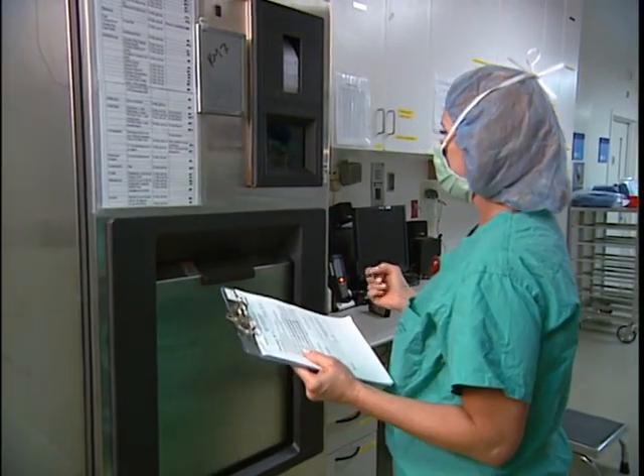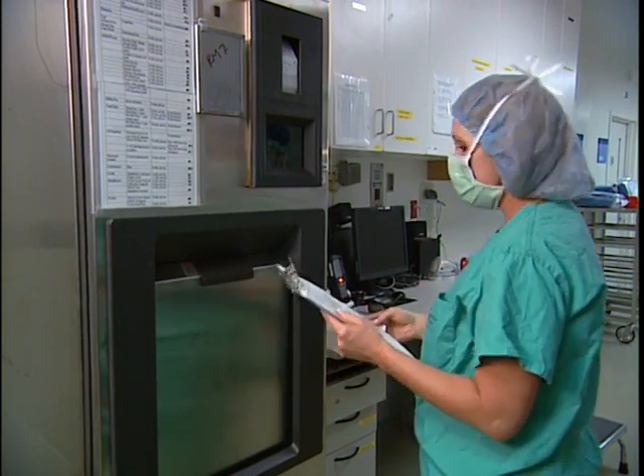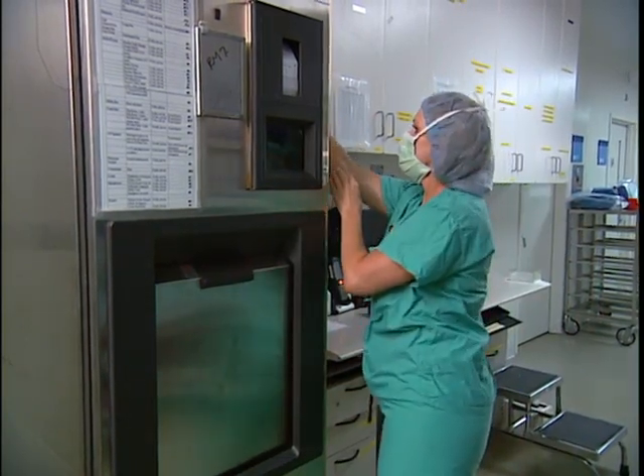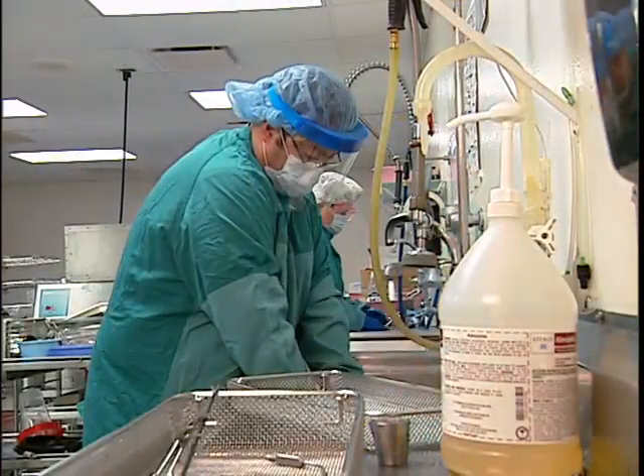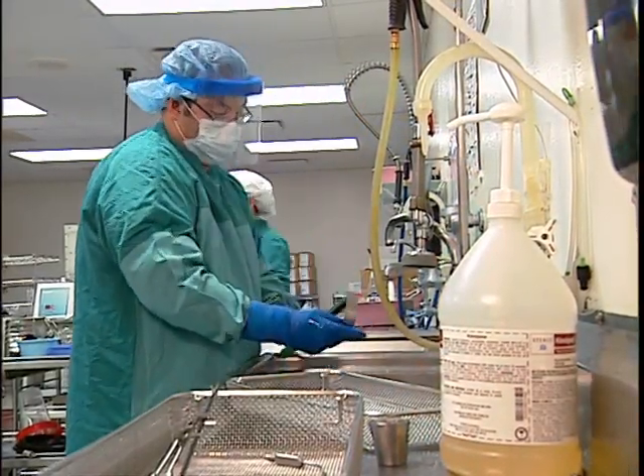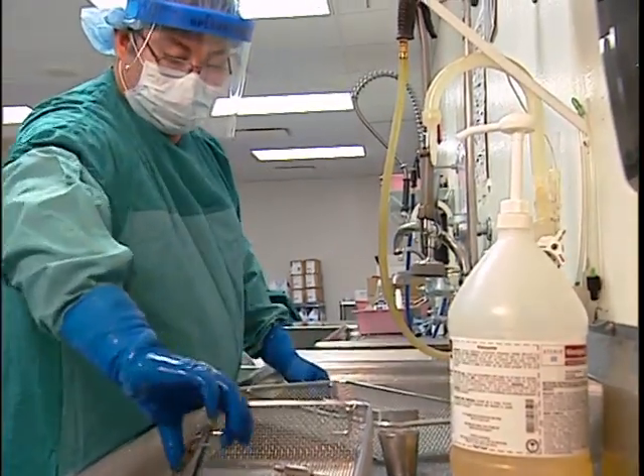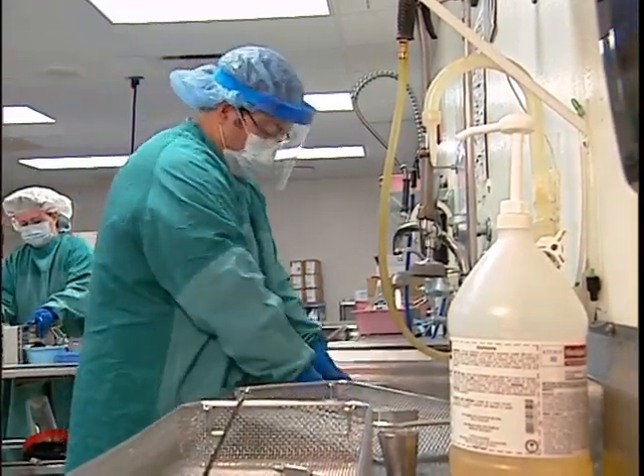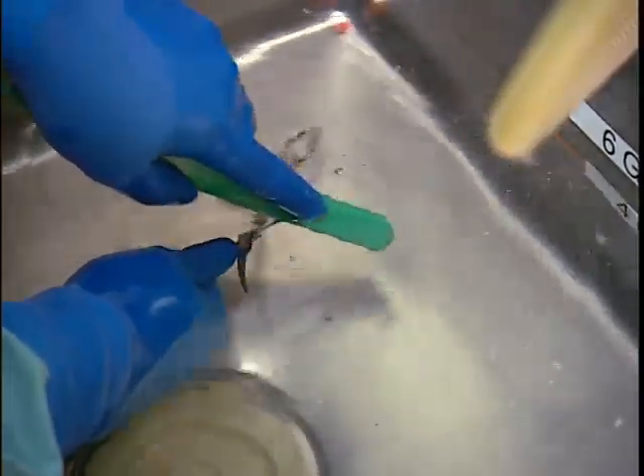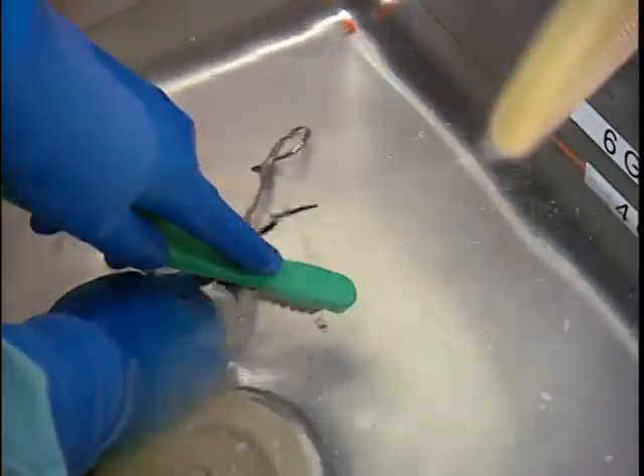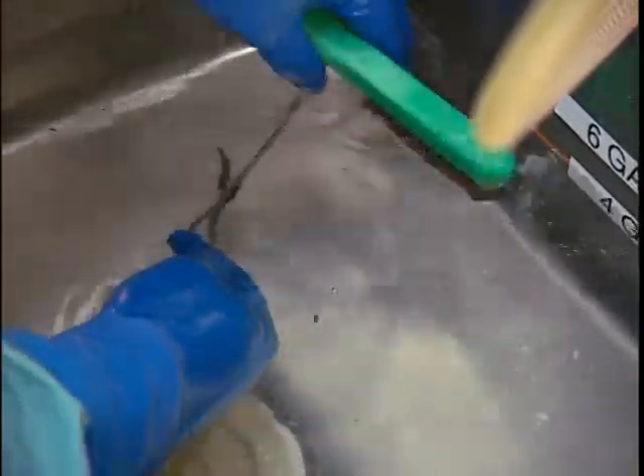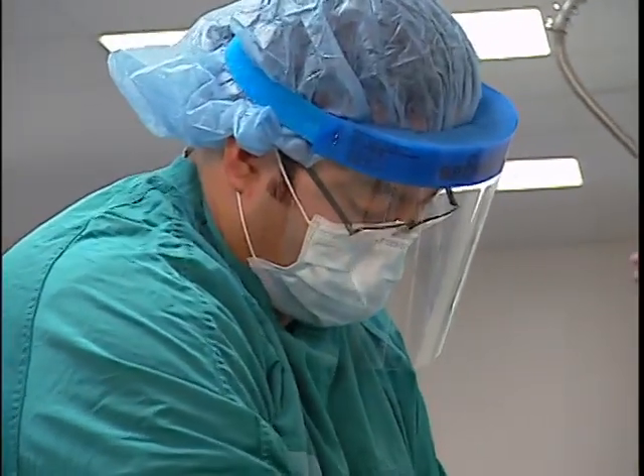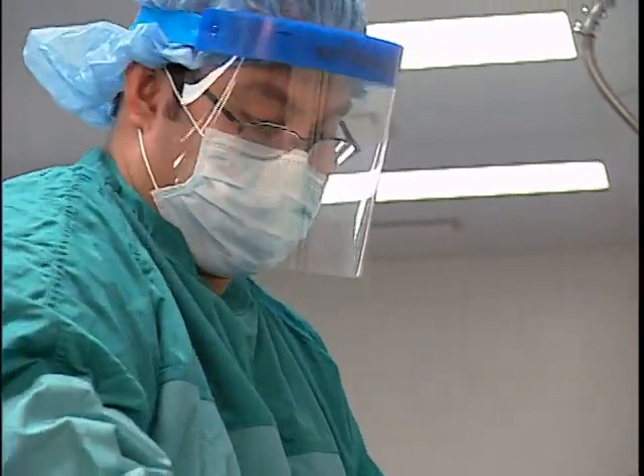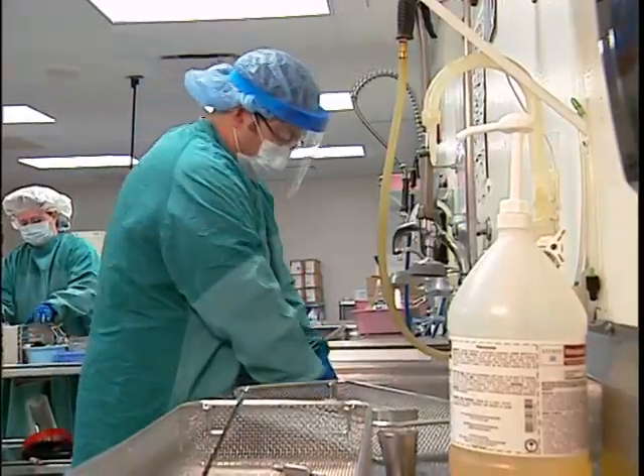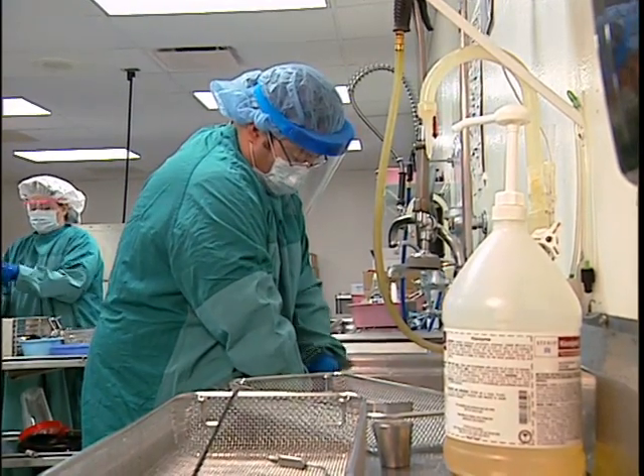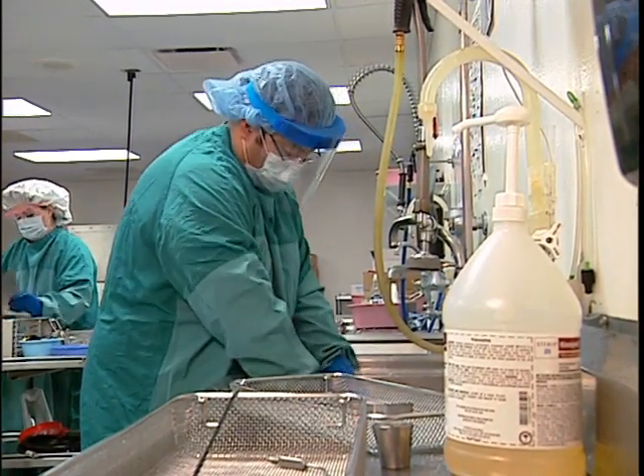Let's highlight the important steps in using immediate use steam sterilization by performing an immediate use steam sterilization cycle. To begin, the item should be disassembled and thoroughly cleaned to remove soil, blood, body fats, and other substances. This process is absolutely essential and should take place in a dedicated dirty area and never in a scrub or hand sink. Be sure to follow all the required processing steps suggested by the device manufacturer for either manual or mechanical cleaning and for the selection of detergent or enzymatic cleaners.